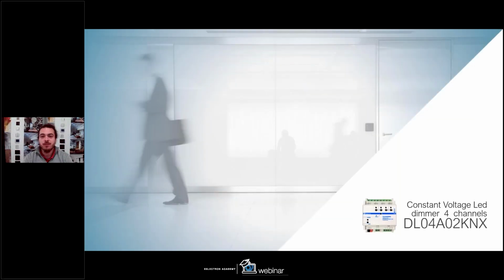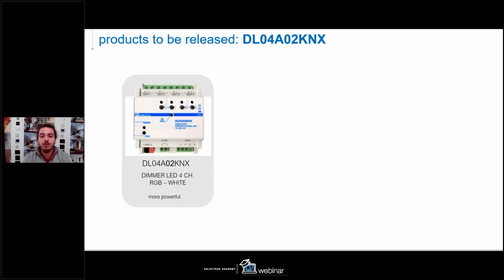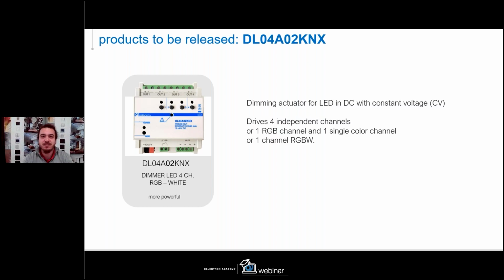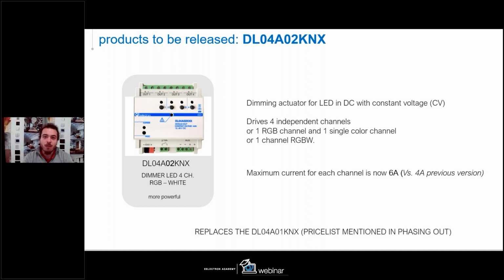Going ahead with the product, I want to show you the new constant voltage dimmer for LED control. So it's an evolution of our DL04A01 KNX. Now the code is DL04A02, since it's the second version KNX, where we still have 4 channels as output for the RGB or RGB white control. But in this case, the device is more powerful. This is because the old one has a maximum limit of 4 amp for each output. Now we have the opportunity to wire up to 6 amp for each output. This means that we can wire LED strips that are longer or more powerful than before.